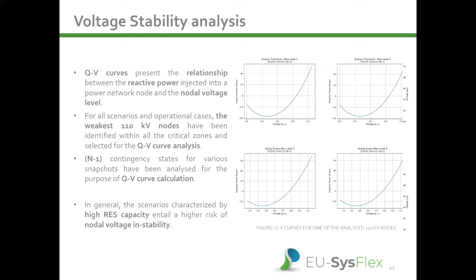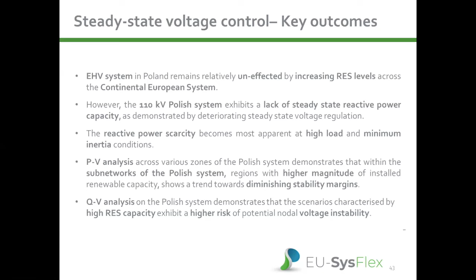Summarizing the final conclusions, the HV grid in Poland exhibits a scarcity of steady-state voltage reactive power capacity. Reactive power scarcity becomes most apparent at high load and minimum synchronous generation conditions. Generally, a higher level of renewables incorporated results in a lack of steady-state reactive power. PV analysis across various zones of the Polish power system demonstrated that regions with a higher magnitude of installed renewables show a trend toward diminishing stability margins. QV analysis performed on the whole Polish power system demonstrated that scenarios characterized by high renewables capacity exhibit a higher risk of local nodal voltage instability.